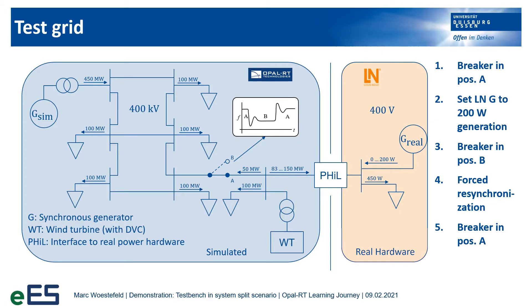The test grid consists of a simulated part with loads, transmission lines, and a wind turbine. The real power-hardware-in-the-loop test bench consists of a real synchronous machine and a resistive load. The wind turbine, which is simulated, is controlled by a grid-forming control structure named DVC. The real synchronous generator is set up as a constant power feeder with low inertia. At the beginning, we have a power flow of about 50 MW from our wind turbine to the other part of the simulated grid, in addition to about 450 W of ohmic load on our test bench. The ohmic load will be scaled up so that the simulated grid will see about 150 MW of load.